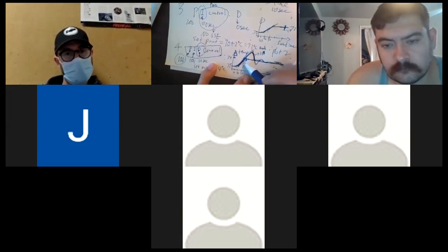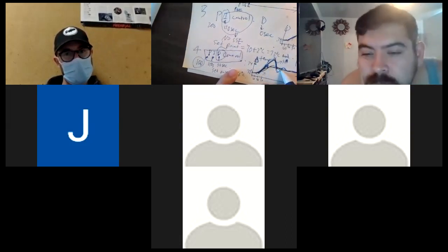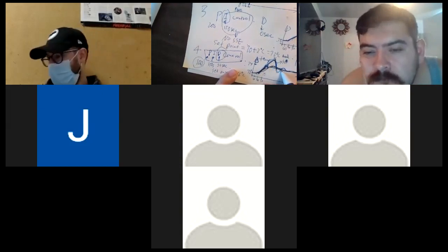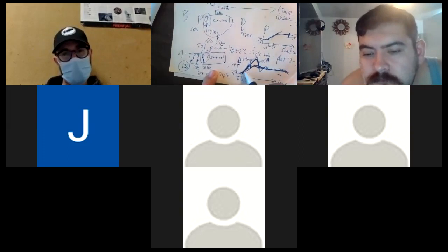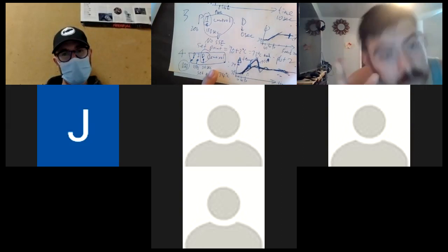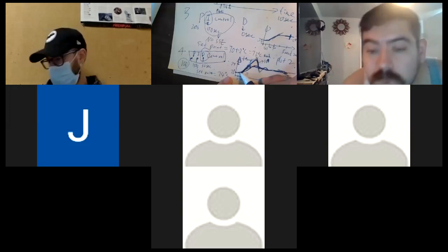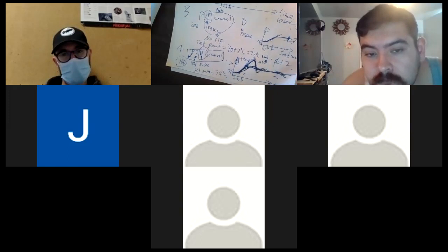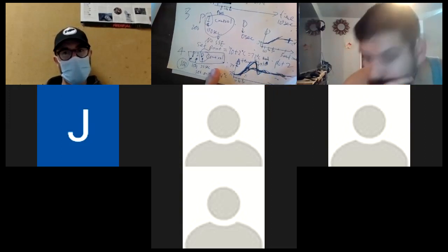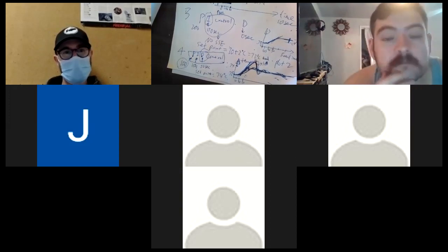I did a little experiment at 100. There is a little bit of overcorrection, like this. Not as significant. It's like 0.1, 0.2 degree above, and then settles down. If you change it to 50, it's not 0.1 or 0.2 degree above. It's like 3 degrees above, 2 degrees above. That will be way overcorrect. So if you see that happen, that means too much proportional gain. You need to halve it, lower it.